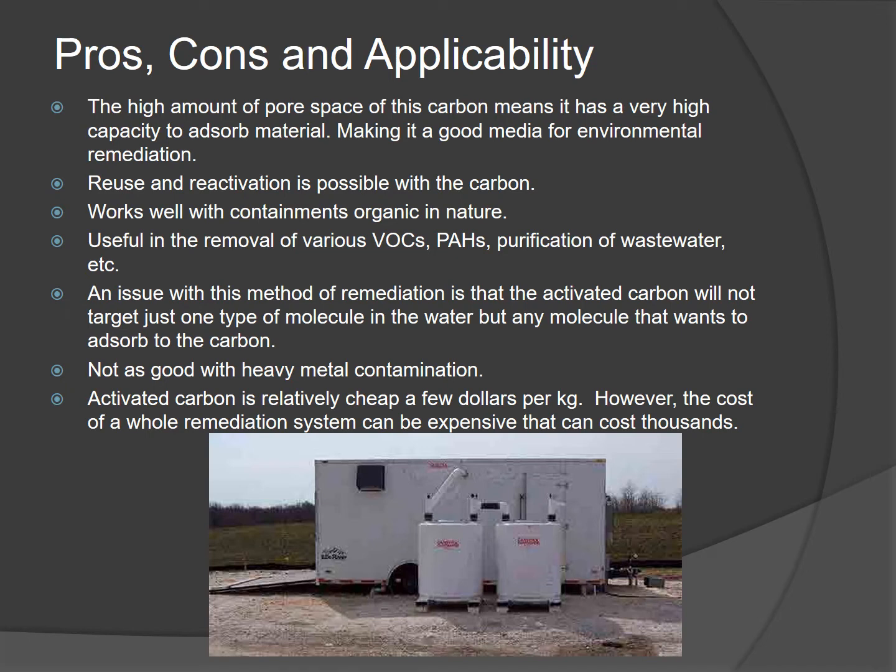Well, some benefits are that carbon has a high amount of pore space, which means it has a very high capacity to adsorb material, and the material in this case is contaminants. Once activated, it can be reused and reactivated. It works well with contaminants organic in nature, and a lot of groundwater contaminants are. So it's useful with removal of various VOCs, PAHs. It can be used for purification of wastewater and other things, and all of those have organic compounds in them.